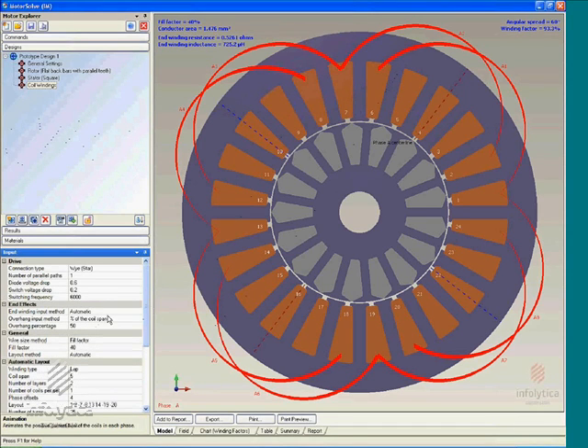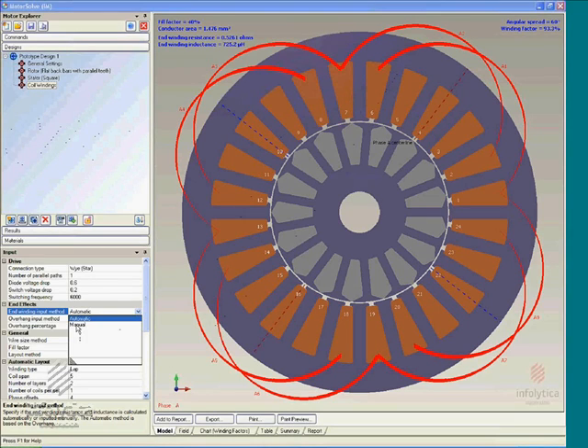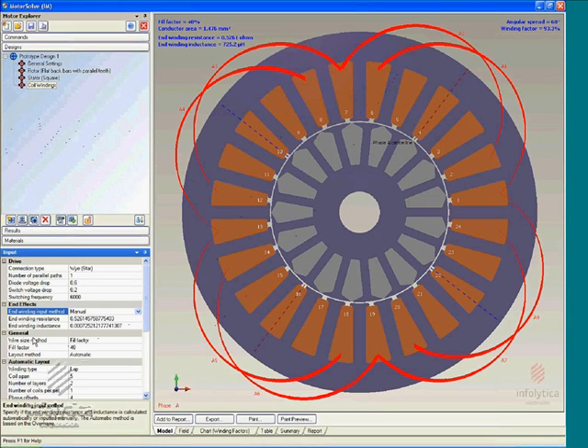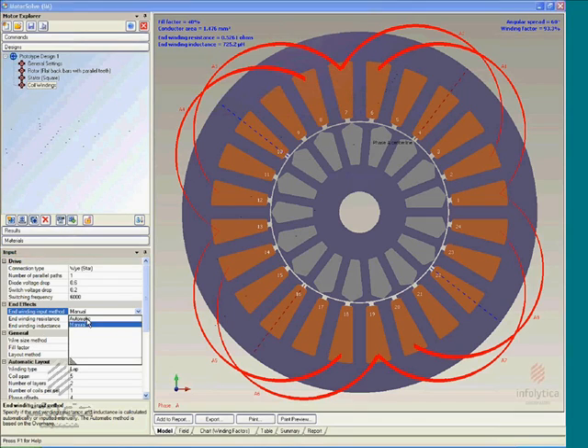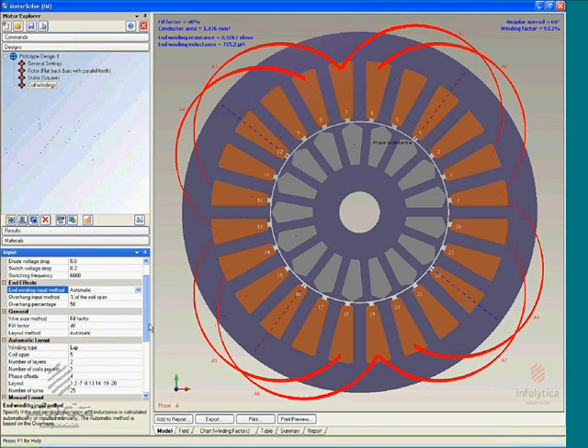We are also able to take into account end effects of the windings, which can be done automatically or by using a manual method — specifying the resistance and inductance, similar to how end windings are taken into account for the rotor bars. The methodologies differ for the actual model used, but the key point is that we are able to take end windings into account in our calculations.